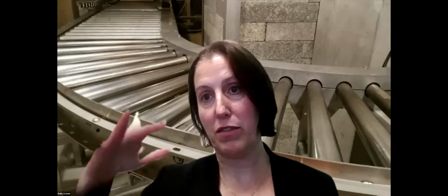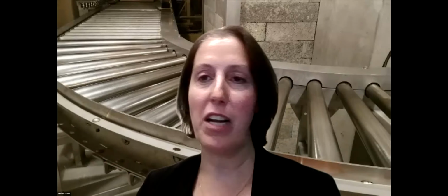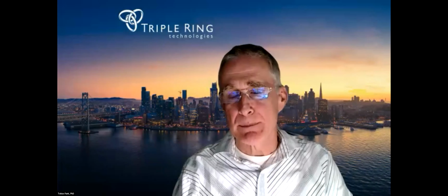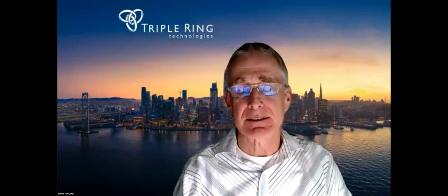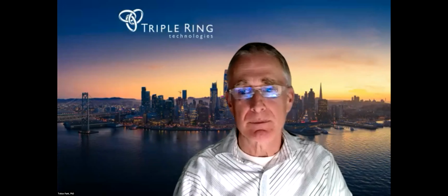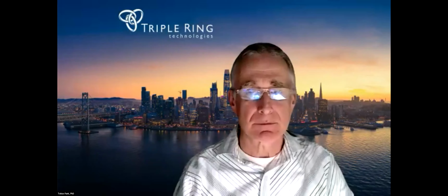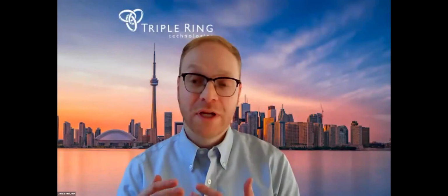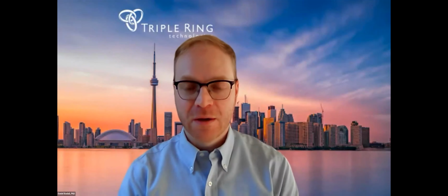I know one thing that we're trying to do from an ISO level, 11137-1, which is the governing radiation sterilization validation document, is change that language so that it speaks less about dosimeter or dosimeter system measurements and more about dose measurements. So we're trying to be a little more flexible in terms of what a dose measurement actually is, and that can certainly open the door. But again, when we think about dose modeling, PQ is one portion of a very large submission package. One aspect that is already allowed from a regulatory standard is determining where the minimum and maximum dose position is. So that can be done by modeling. Yeah, that's in ISO 11137, and it doesn't put any constraints on the modeling system because ultimately you then have to put a dosimeter in that position to do the measurement.